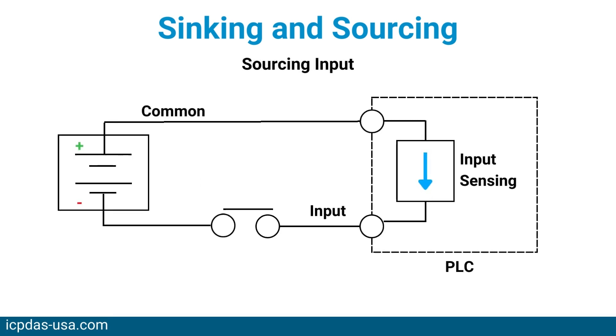The device receiving the signal provides power for the input signal. It must be connected to a sinking output, such as a two-wired transmitter, which uses the power from the receiving device.